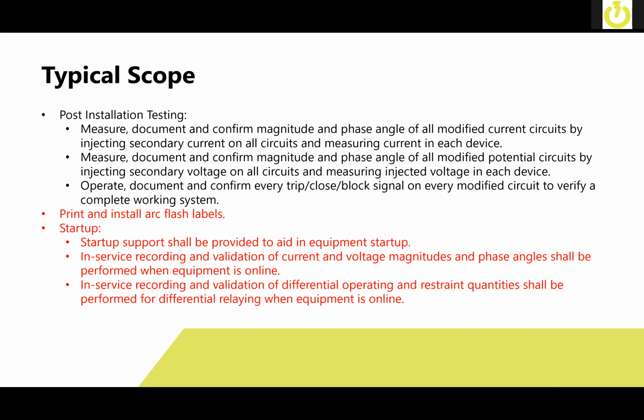From a post-installation standpoint, it's recommended to measure, document, and confirm the magnitude and phase angles of all modified current circuits by injecting current on all those circuits and measuring the current in each device. Depending on your application, you may want to go all the way back to the current transformer in the system, or you may choose to decide to go back to the next closest location that was unmodified within the system. From a voltage standpoint, measure, document, and confirm the magnitude and phase angle of all modified potential circuits by injecting secondary voltages on those circuits and measuring it in each device.